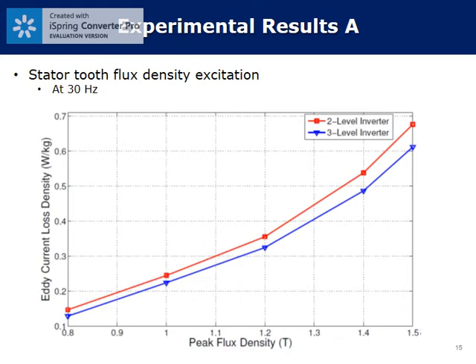So the eddy currents, as you can see, you have more loss density for the 2-level inverters compared to the 3-level inverter. 1.2 up to 1.5 Tesla. We had limitation on the hardware itself, because to get more flux densities into this yoke, we need a bigger amplifier. So we had a limitation of the amount of currents we could really inject into this thing.